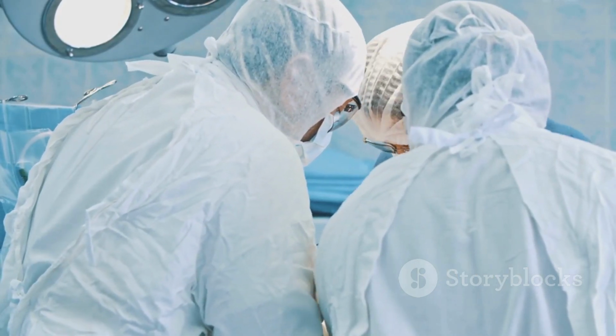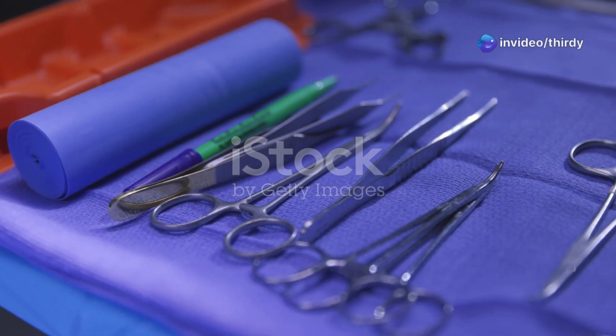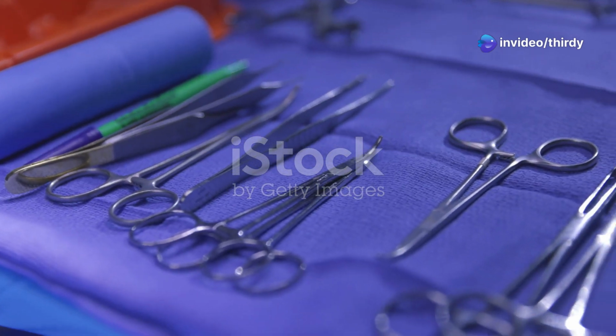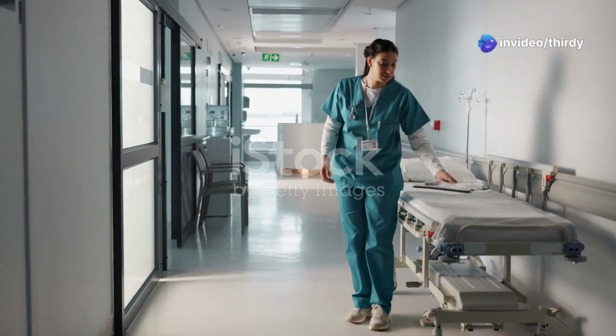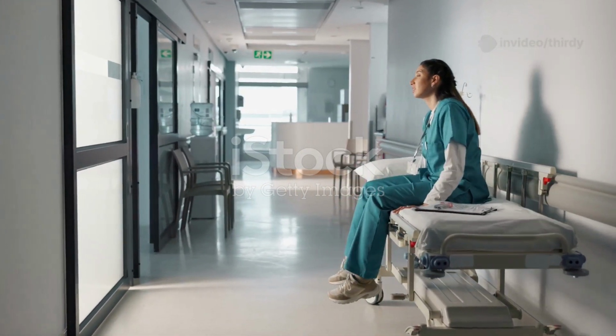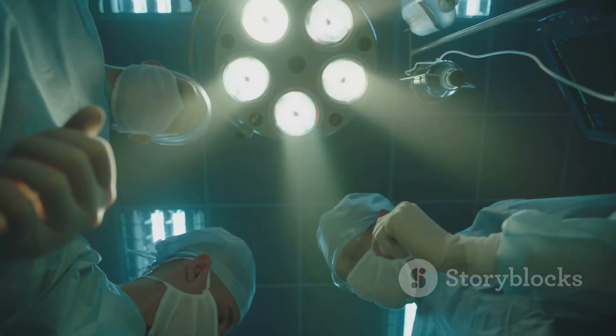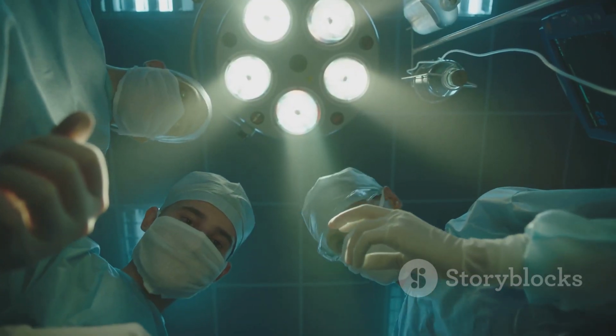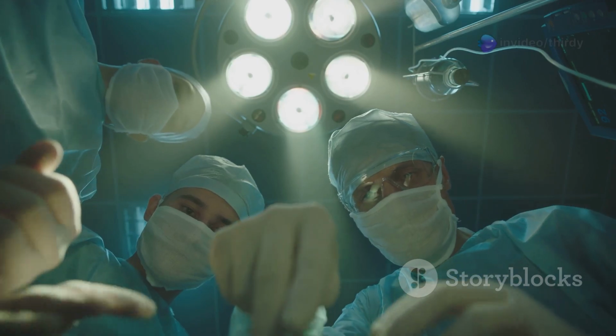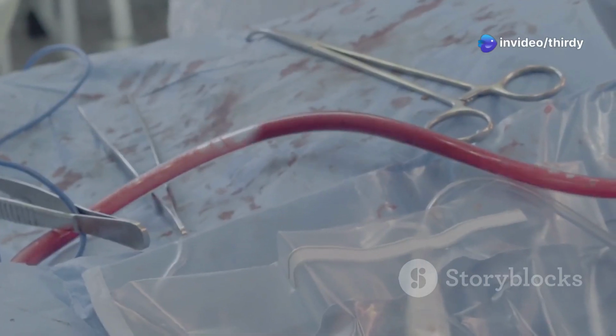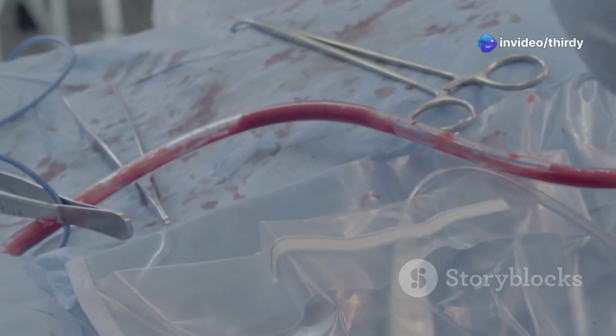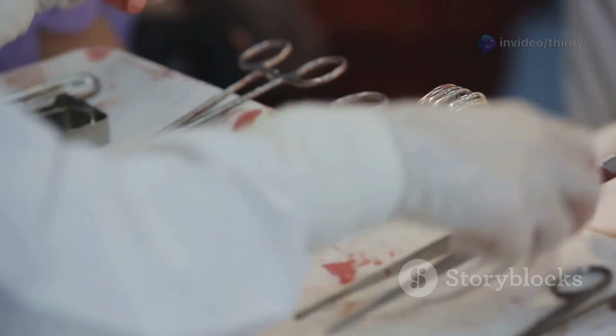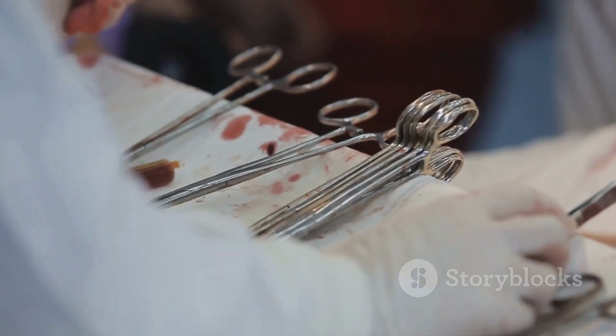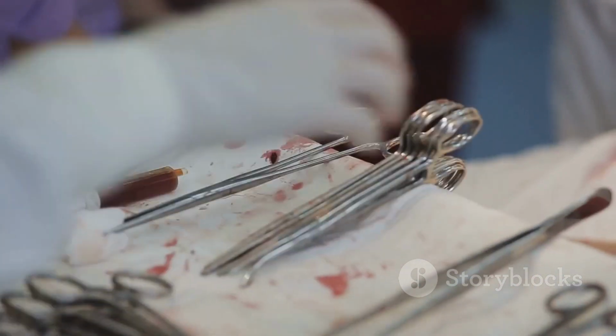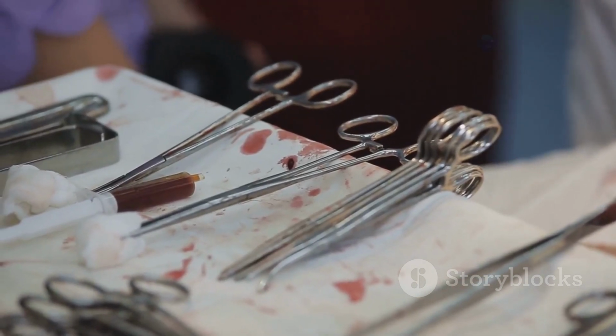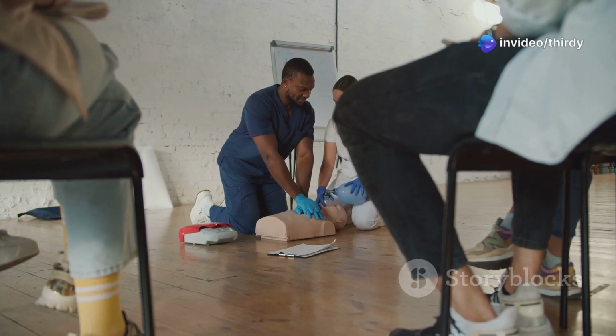Despite clear guidelines, failures in surgical instrument reprocessing happen more often than we'd like to admit. One of the most common weak points is human error, often driven by pressure to work quickly. When surgical schedules are packed, technicians may feel rushed to turn over instrument sets, leading them to skip crucial seconds of manual scrubbing or overload washers and sterilizers. This pressure can result in instruments that still have hidden bioburden, which, as we know, prevents effective sterilization. It's a dangerous shortcut. Inadequate training is another major pitfall.